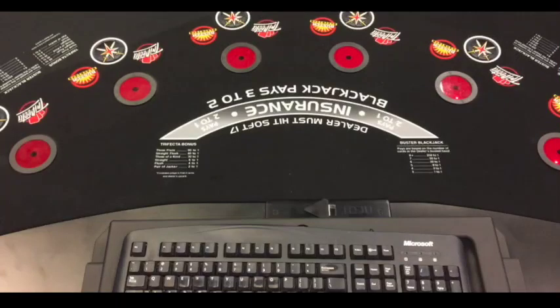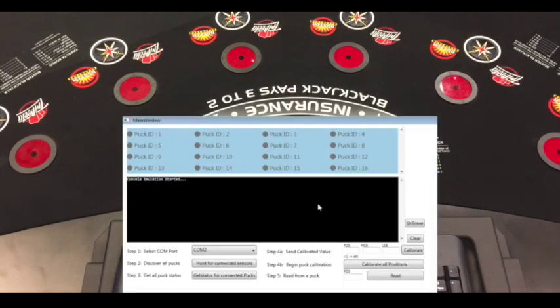I'm putting this video together to give us a better understanding of what the calibration process is for the sensors. You're not actually calibrating the sensor. You're calibrating the hub to the sensor that's connected to it. We're going to go in, run the normal calibration application. We're going to hunt and get connected status.